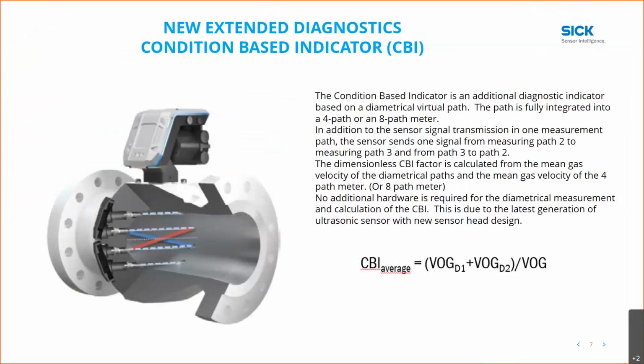So that's one of the new diagnostics that's available. It's also available on the 4-path. There's no additional hardware required. When you buy a 600 XT 4-path or 8-path meter, this feature is already in there with no additional hardware needed. And this is, of course, due to the latest generation of ultrasonic sensor and also a new sensor head design. So we'll talk a little bit more about that in a minute.